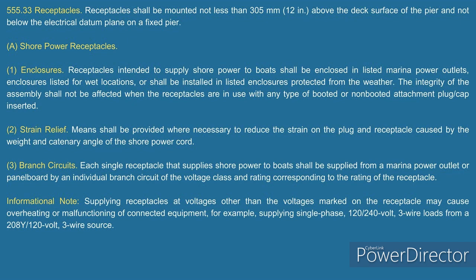It's outside. It's getting rained on and everything. Why don't I have GFCI for that receptacle there? Yeah. There's certain equipment they tell you to have GFCI protection, okay, and it's the equipment that's providing the protection. And I'll add another point. Code-making panel 2 went in, and then they come back after the fact and said, "Oh yeah, the AC unit, there's an outlet there, and you've got to have GFCI protection."